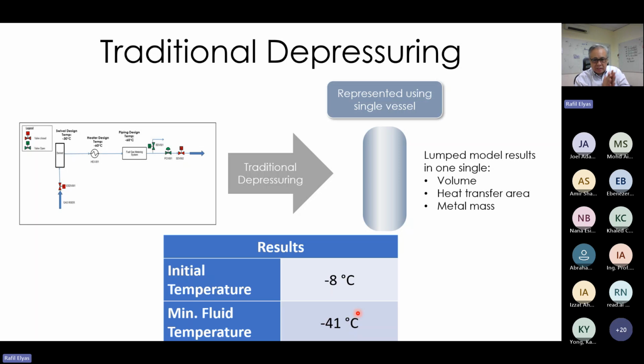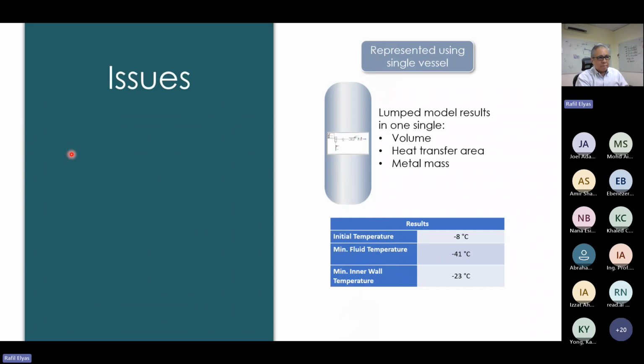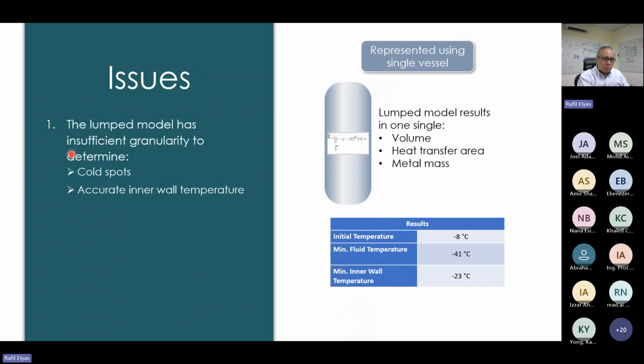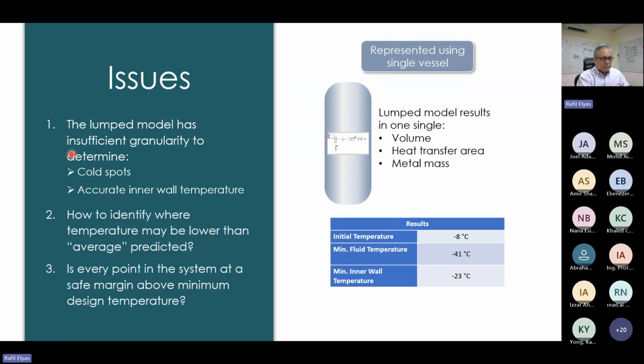Obviously, the inner wall temperature may be higher than minus 41, but this was a bit disconcerting because it's just like a single lump. And you can see that thicknesses are going to vary across here. If you lump everything together, you can't really tell where that low temperature spot is. If it's happening around here, I don't really care so much. But if somewhere around here, around the swivel, and this area, I'm getting minus 41, then I have some issues. So you can't find out where the cold spots are. You don't really know what the inner wall temperature is. So it's difficult to determine whether all the points there are above the safety margin, above your design temperature.